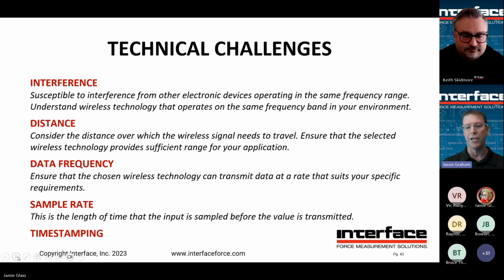Is it something relatively close? Can we get through walls? Will we need a repeater? Are we looking at something where repeaters aren't sufficient, or wireless is impossible? Data frequency - what's the distance? Sample rate - is it sufficient, fast enough for whatever you're going to be doing? Sometimes wireless isn't fast enough and we need to go wired. Time stamping and synchronization - is that a key thing for you?